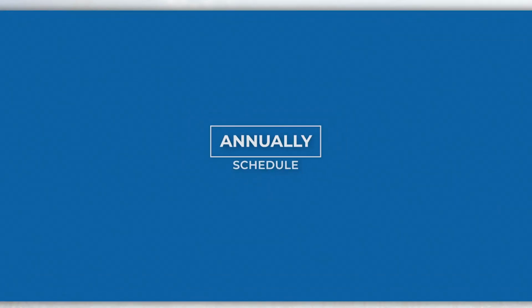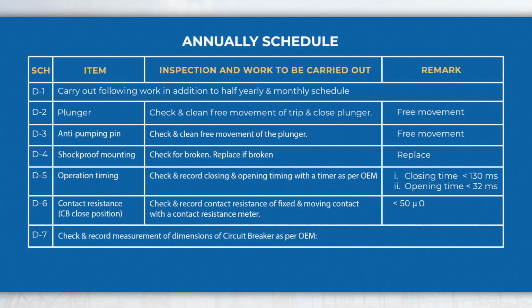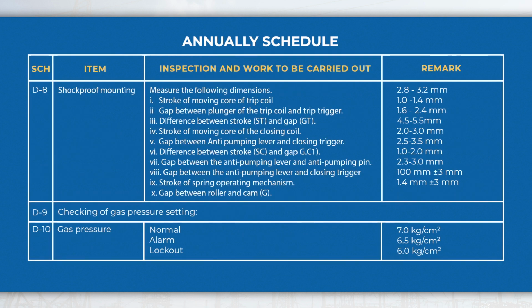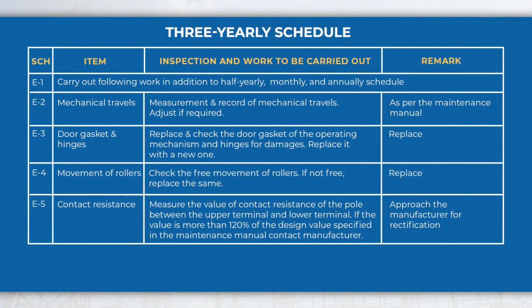Annually schedule. In the annually schedule, perform the activities like checking the plunger for free movement, measuring the operating time, contact resistance, checking gas pressure, etc. in addition to half-yearly and monthly schedule activities. 3-yearly schedule. In 3-yearly schedule, perform the activities like checking the mechanical travels, doors and hinges, movement of rollers, etc. in addition to annually, half-yearly and monthly schedule activities.